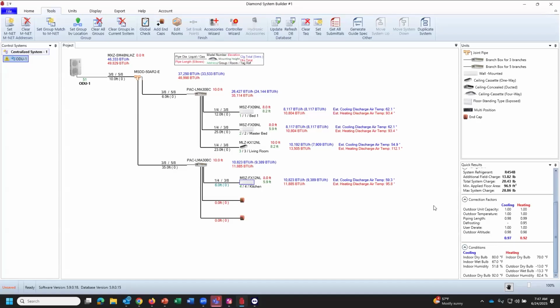And so if you've got a house that fits these needs, if you've got a house that actually comes back with right around that 4 ton actual cooling load necessity, this is actually an ideal system. And each one of these rooms, like we were pointing out with this FX09 and this small bedroom right here, that's almost an 11,000 BTU output. That's pretty substantially oversized in most conditions. So it is one of those things that should be looked at, whether or not it's something that you choose to address.